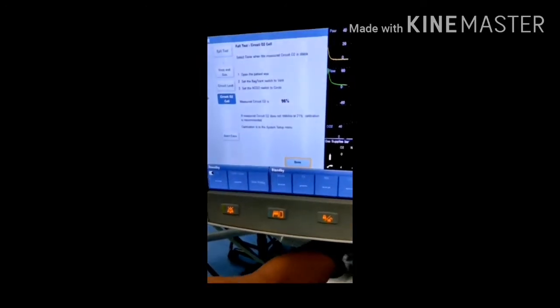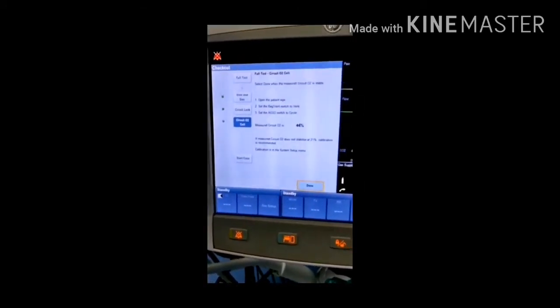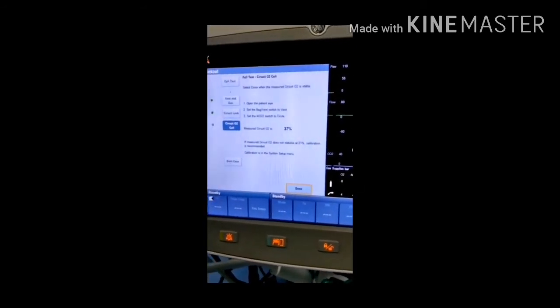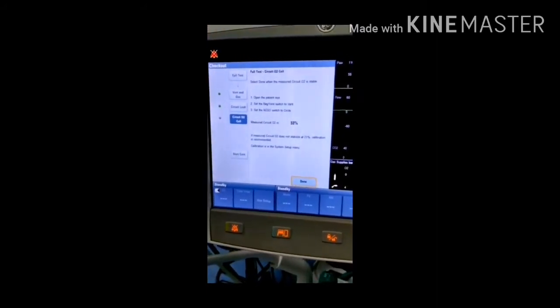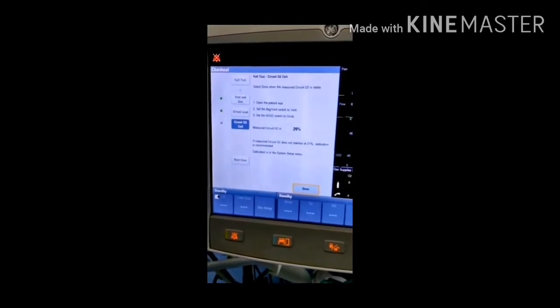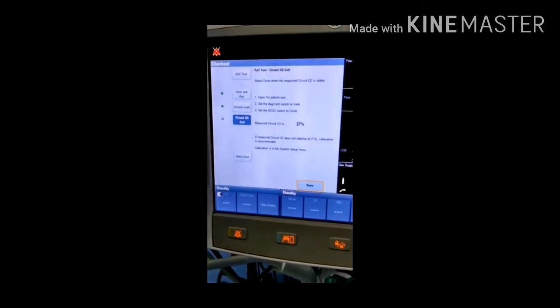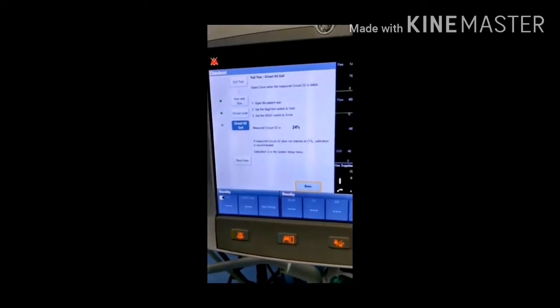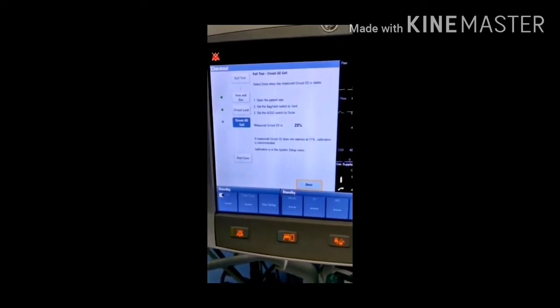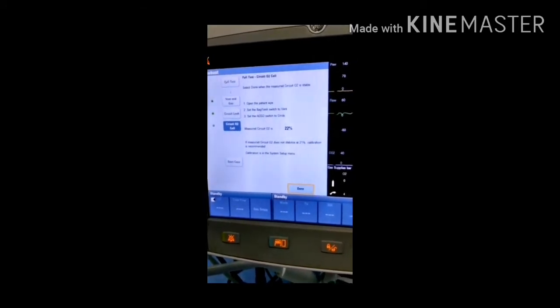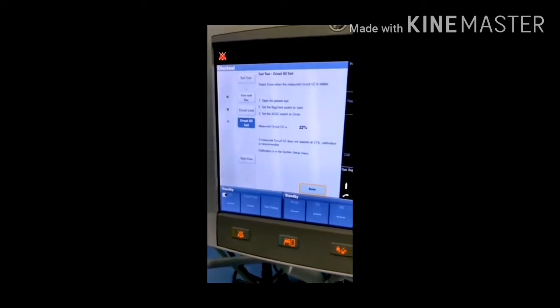We will open the patient Y for that. We will set the bag to vent switch again and the ACGO to circle. We have to check that the O2 percentage is stabilizing at 21%, which denotes that it is working properly. In case the calibration is not completed, and it is not getting stabilized or coming to 21%, you need to change the O2 sensor. At times, even if the calibration is not done and not checked, you get a message on the screen to replace the O2 sensor, which also denotes that you have to replace the O2 sensor.